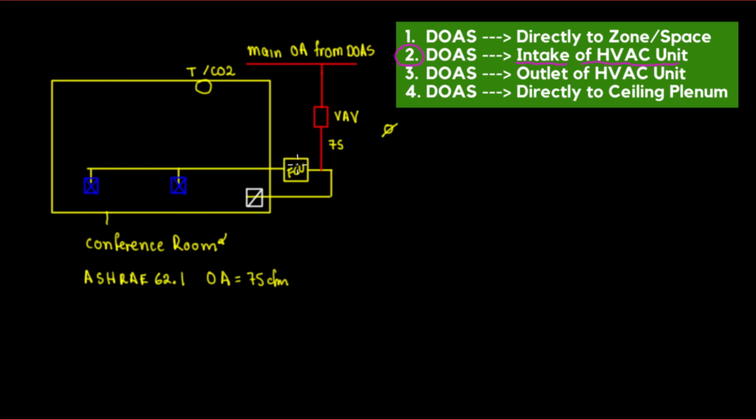All right. The FCU, we remember from the heat load calculation, this space required 1 ton. So this is equal to a 1 ton unit. For the 1 ton unit, based on the cut sheet that we saw in the previous video, the CFM was 370. That's at maximum speed. From 370, we decided we're going to do 185, but that depends on the designer, right?